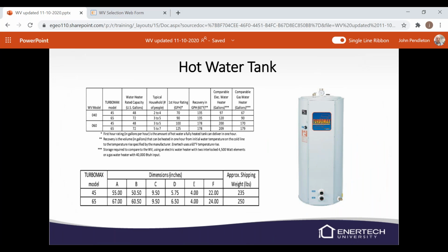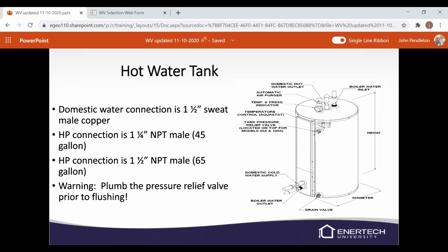Again, we kind of talked about the hot water sizing. These are all listed in the IOM. You need to size it. And then we also list some dimensions of the tank itself. Domestic hot water connection is a 1.5-inch sweat male copper fitting.